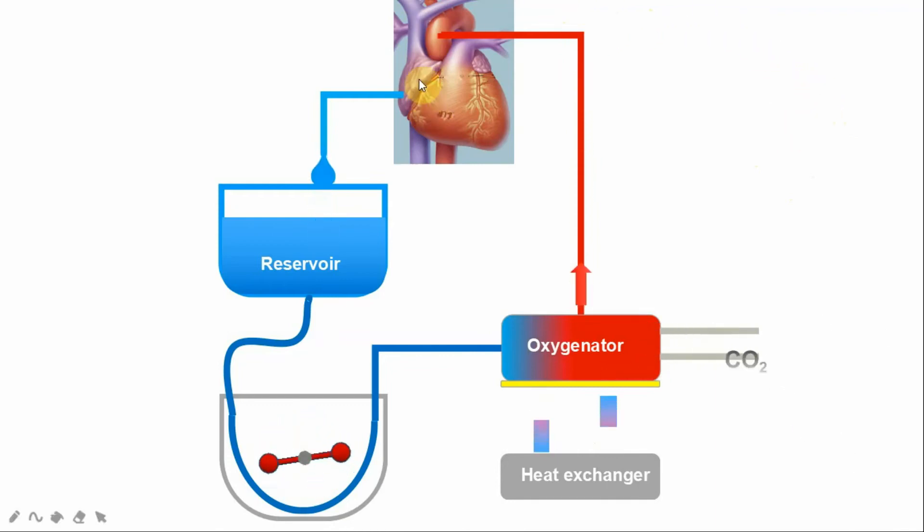Let me summarize again. We are taking the deoxygenated blood from the right side of the heart, superior vena cava, inferior vena cava, putting to the reservoir. This blood is then transported to the oxygenator, and the function of the oxygenator is to add oxygen, remove carbon dioxide, and optimize the temperature. Once that is done, this oxygenated blood is then pumped into the aorta, and that oxygenated blood is transferred to the rest of the body.